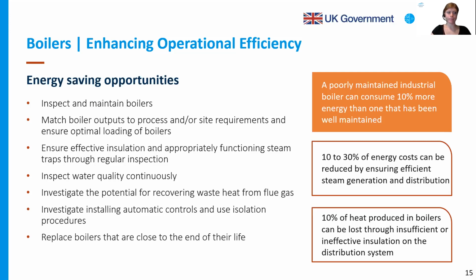Typically in a plant, 10% of the heat produced in a boiler could be lost through inefficient or insufficient insulation in the distribution system. Continuous inspection of water quality is also needed. While manual TDS control is the cheapest way to achieve TDS control, it tends to be laborious in nature, and it can often lead to excessive thermal loss, especially when you have frequent blowdowns.